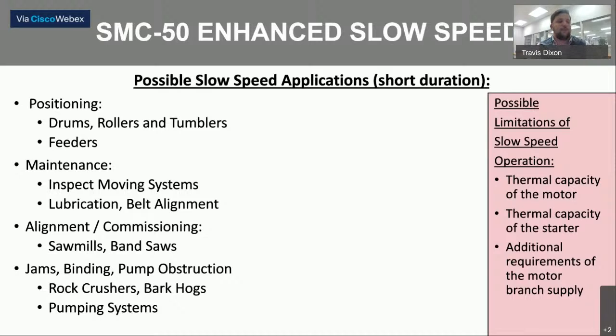You can also do 2 programmable slow speed references. You can switch in operation between slow speed 1 and slow speed 2 with a terminal input. It's used for positioning, maintenance, alignment, like aligning a bandsaw, a loaded versus unloaded conveyor, a rock crusher, some of that. The limiting factors there are obviously the thermal capacity of the motor and the starter, and whatever additional requirements of the motor branch supply.